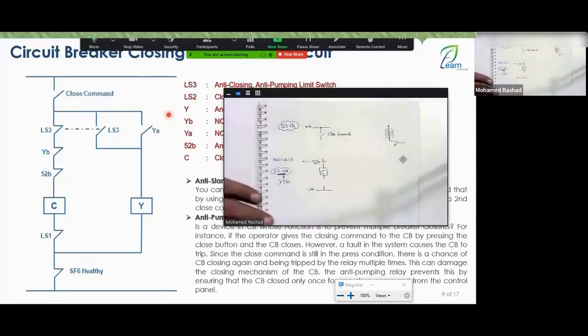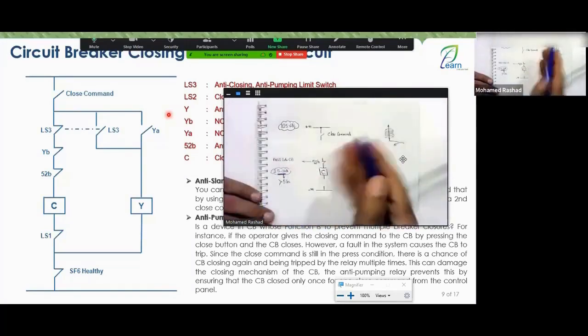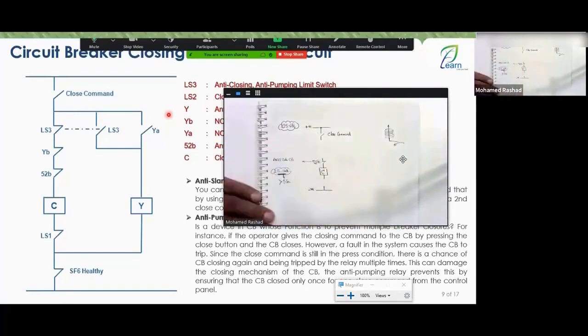For example, if I tell you 24, you'll immediately understand that this means overflux. 21 means distance. 87 means differential protection. 52 means circuit breaker. Each number means something. And it means normally closed contact.